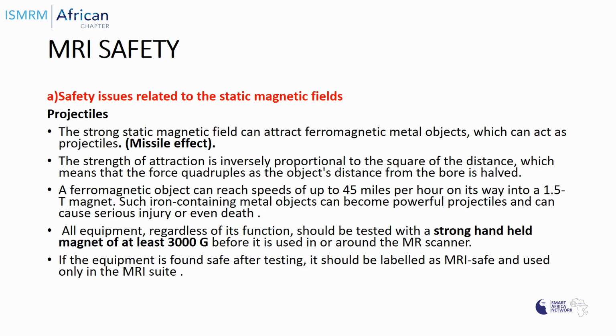Such iron-containing metal objects can become powerful projectiles and can cause serious injury or even death. Hence, all equipment, regardless of its function, should be tested with a strong handheld magnet of at least 3000 Gauss before it is used in or around the MR scanner. If the equipment is found safe after testing, it should be labeled as MR safe and used only in the MR suite.